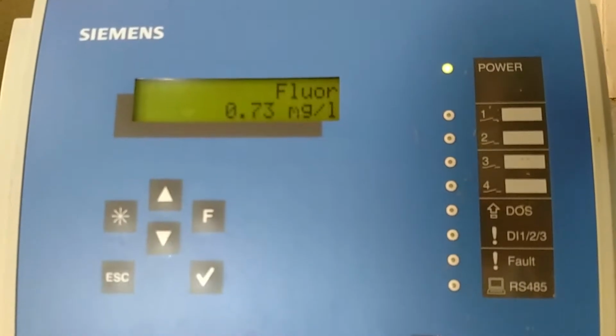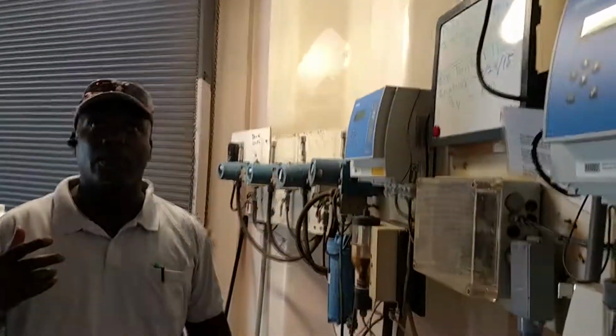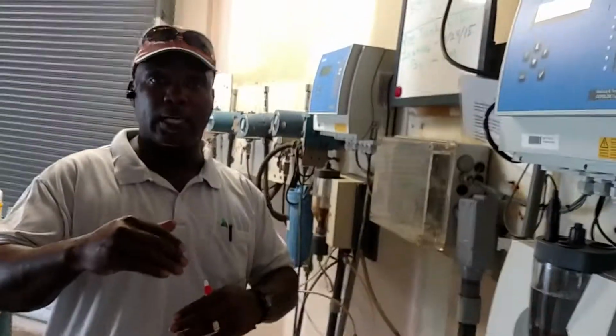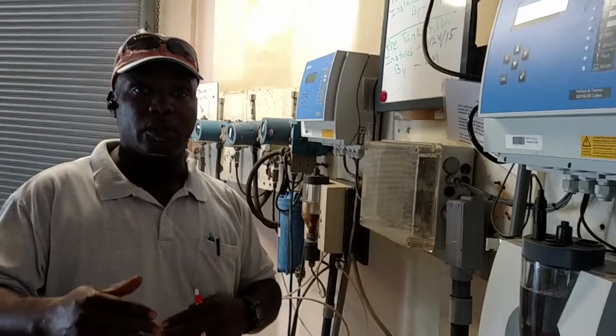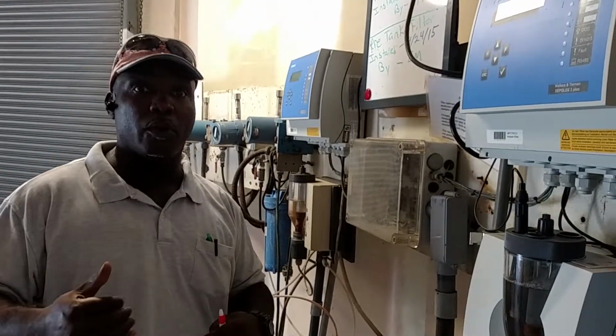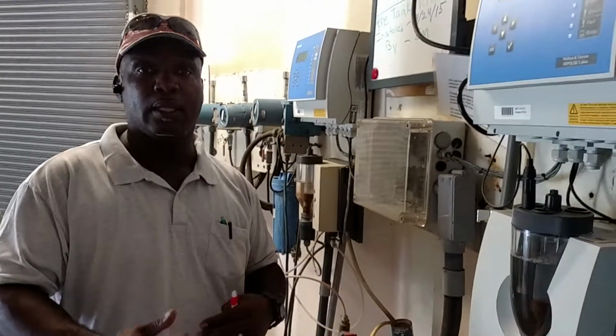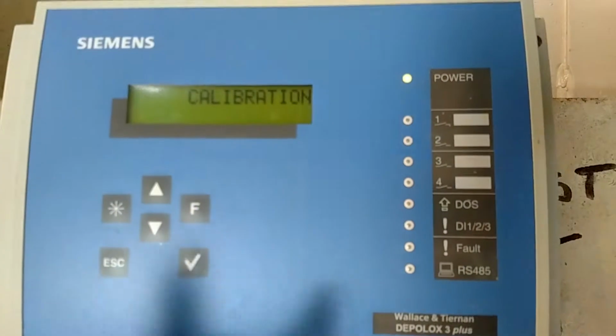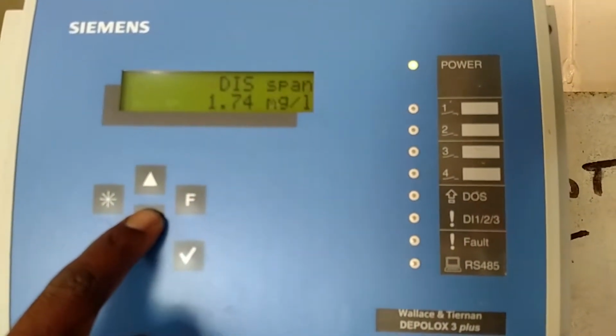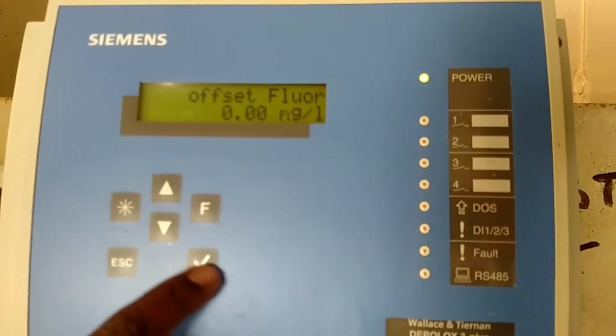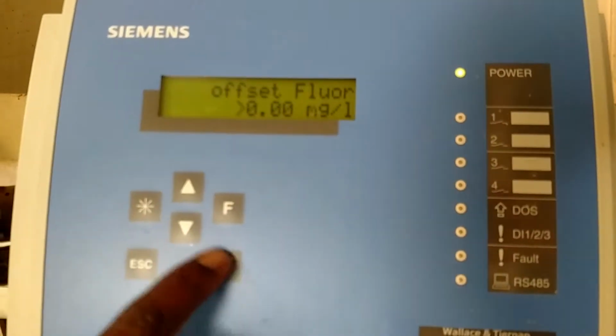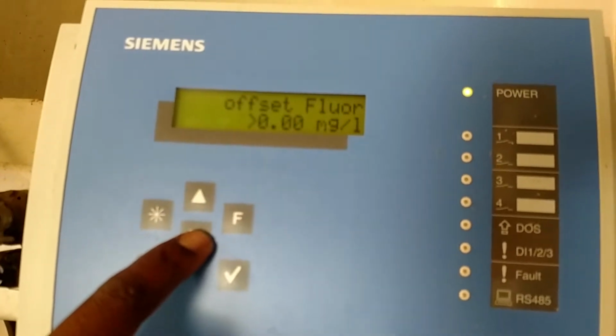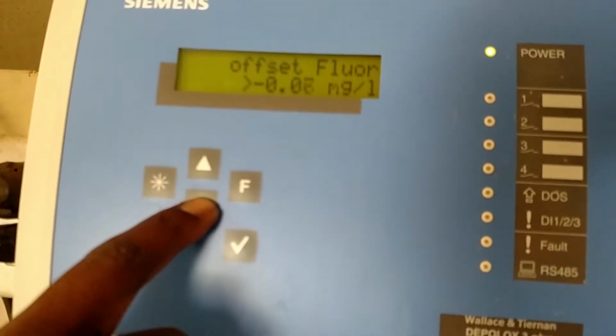And just so you'll know, sometimes I had to do it at water plant 4, and I also had to do it at water plant 1. If you calibrate and everything comes out good, but you see that their daily grabs are off, I think at water plant 4 it was like 1.2, and the grab was basically 0.8. So what you do then, if that's the case, you come here, hit the F to get into the calibration mode. You can scroll down till you get to offset fluoride, and then hit the check mark, and we're basically going to put a negative 0.4 in there. That's what we actually would have put in there.